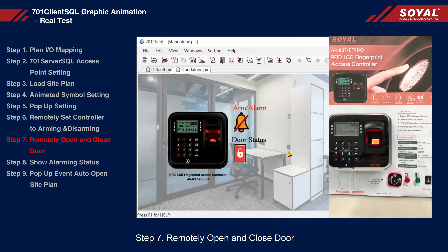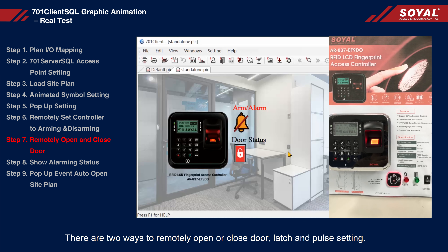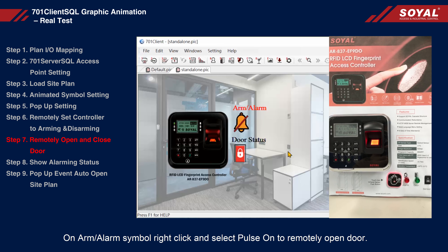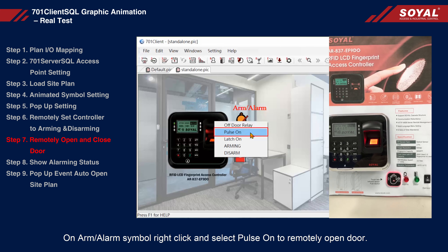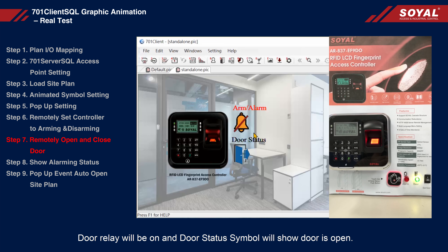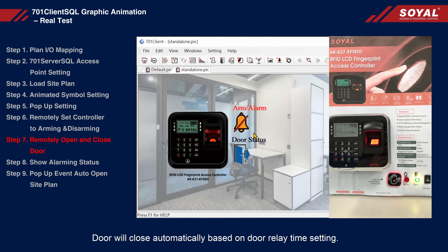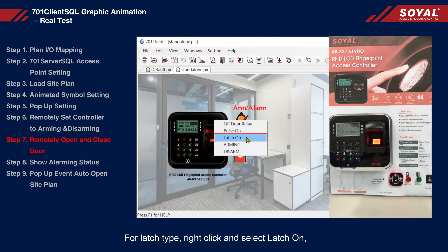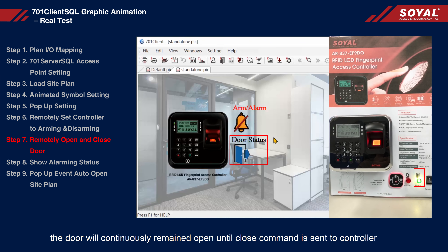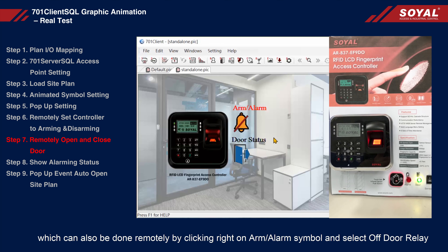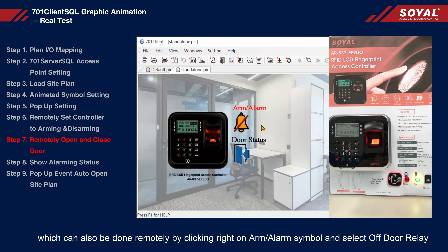Step 7: Remotely open and close door. There are two ways to remotely open or close a door: latch and pulse settings. On the arm/alarm symbol, right-click and select Pulse On to remotely open the door. The door relay will be on and the door status symbol will show door is open. The door will close automatically based on the door relay time setting. For latch type, right-click and select Latch On. The door will continuously remain open until a close command is sent to the controller, which can also be done remotely by right-clicking the arm/alarm symbol and selecting Off Door Relay.